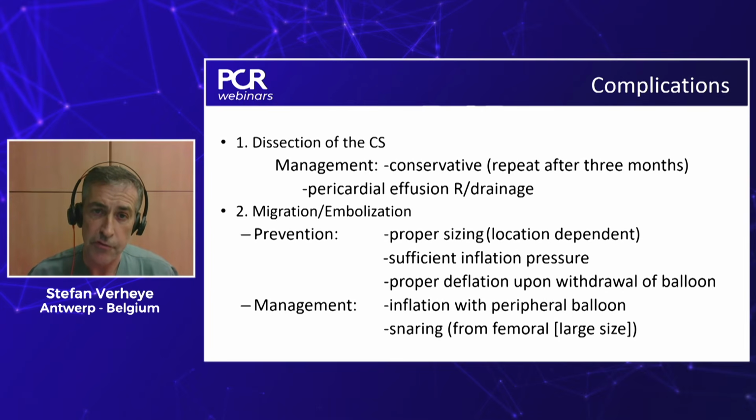So use sufficient inflation pressure. Don't go too high, but high enough. You need to have a step up and a step down. And again, also what Martine has alluded to, a proper deflation upon withdrawal of the balloon.